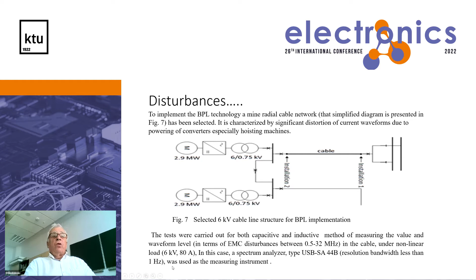We selected for testing the applicability of BPL technology a mine radial cable network. The simplified sketch is indicated here, and this is a bus bar supplying here. There's a cable on which we performed our test and theoretical analysis, and it supplies the selected structure of implementation, the powering converters especially for a hoisting machine. A hoisting machine has very big power, and therefore, due to these converters, some distortion of voltage waveforms and current waveforms appears in this cable. And therefore, we tested under non-linear loads with about 6 kilovolt and 80 amps RMS, using a spectrum analyzer with resolution less than 1 hertz.